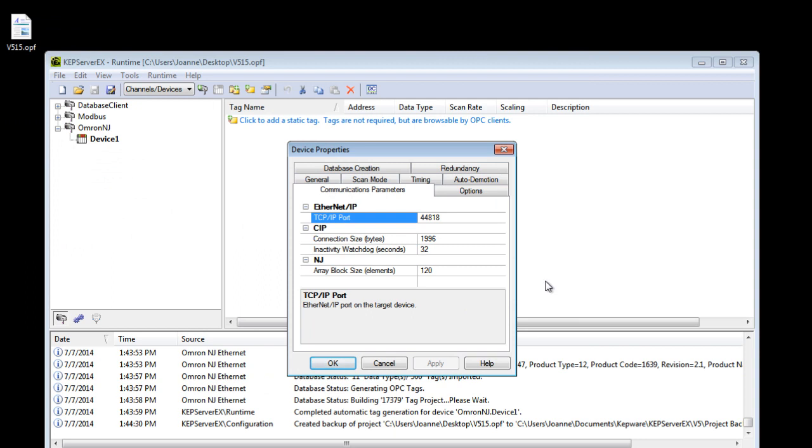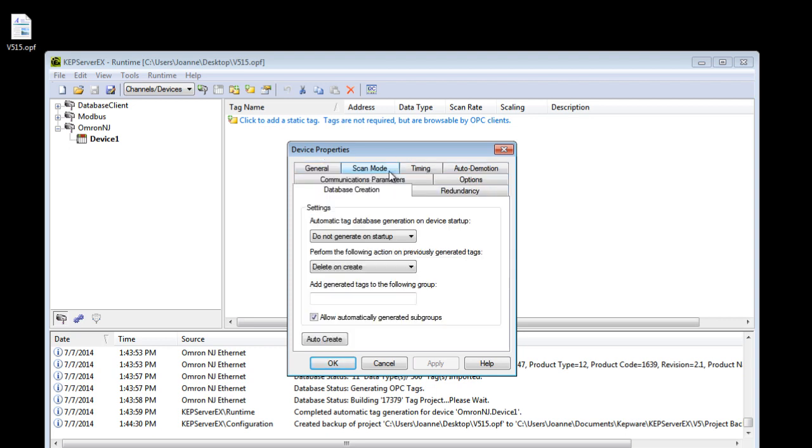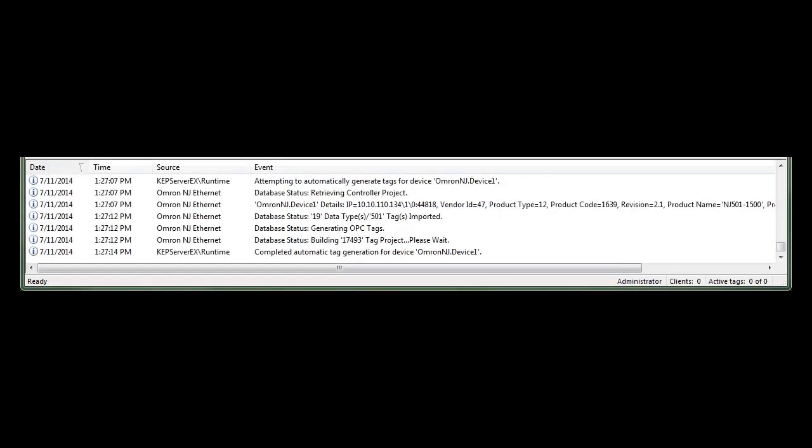Other features are in communications parameters. We can optimize communication speed with the device by adjusting CIP connection size and array block size. Finally, from the database creation tab, I can connect to the device and automatically pull all the program items into my server tag database. I just click auto-create to start the process, and I can see in my event log messages that show the server is contacting the device to pull the program.